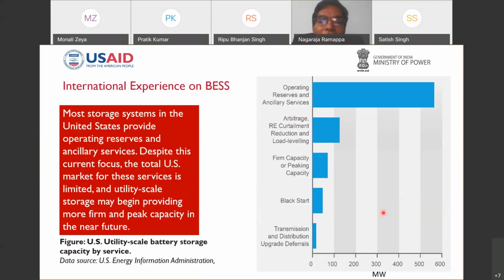Next, please. This is how the battery energy storage system is modeled, and based upon that, and on the international experiences with battery energy storage systems, it has been found that most of the BESS being practiced in the US at present is for the operating reserve and also the ancillary services. Therefore, almost about 550 megawatt of BESS is participating in the operating reserve and ancillary services in the US. The other best example is the Australian system, where they have 100 megawatt. The BESS storage system was installed within 100 days, and the performance is very well appreciated. Next, please.